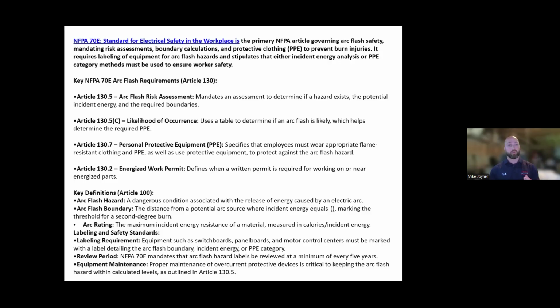It's also delivered with arc flash labels. Labeling is part of the requirements nowadays. Every piece of electrical equipment is required to have an arc flash label. Most places do have some sort of labeling, or if they haven't, sometimes they'll just have a generic danger label, but this one has a proper warning label broken down into the proper PPE and what to wear, the arc flash boundary, your hazard, and the AIC rating.